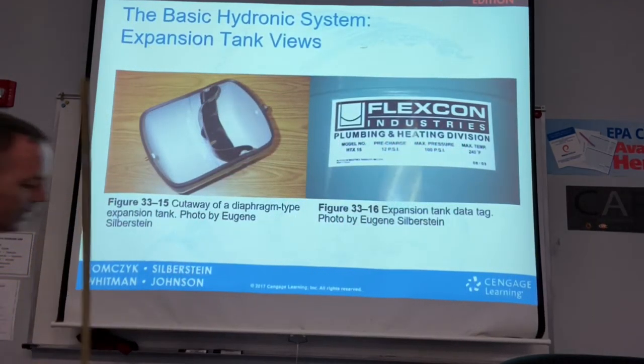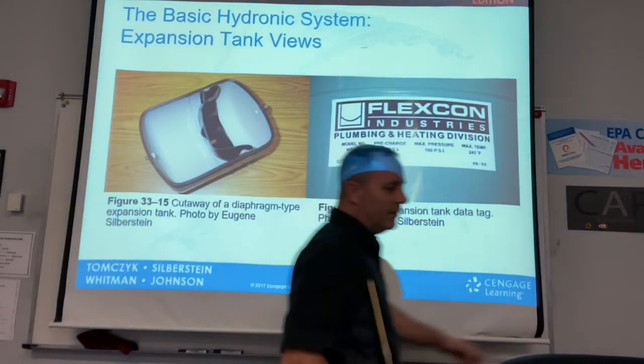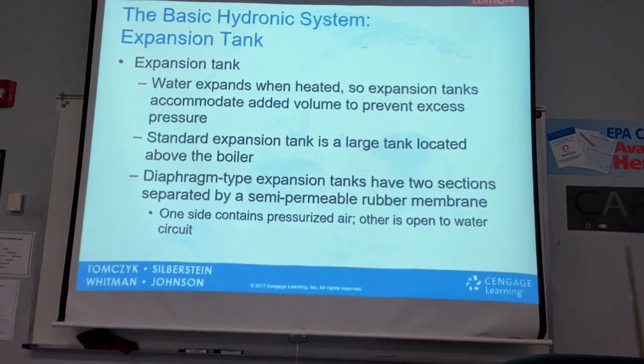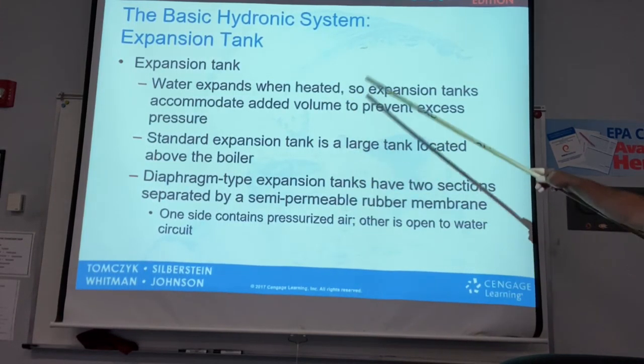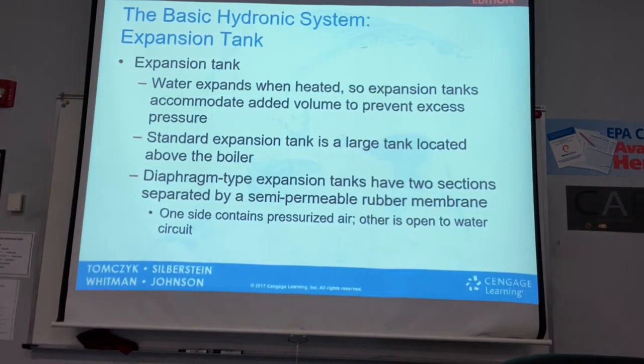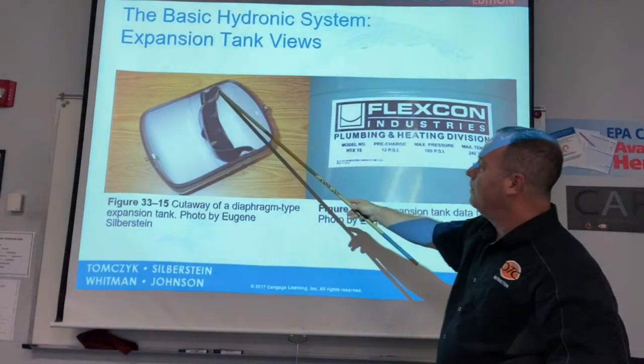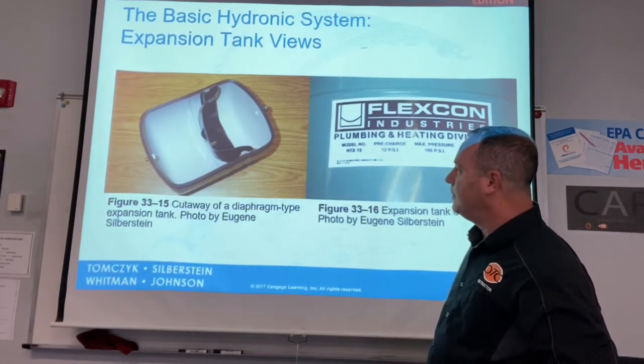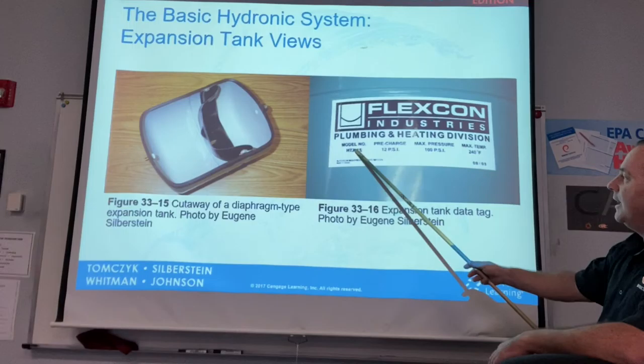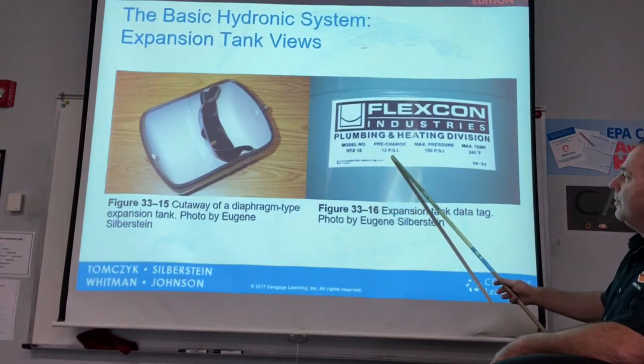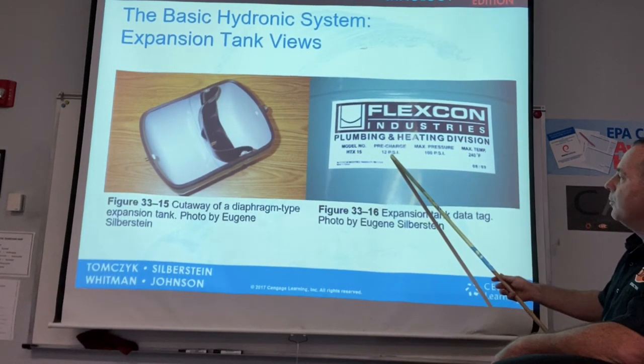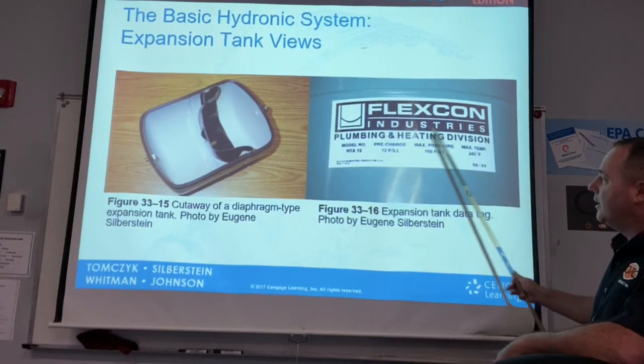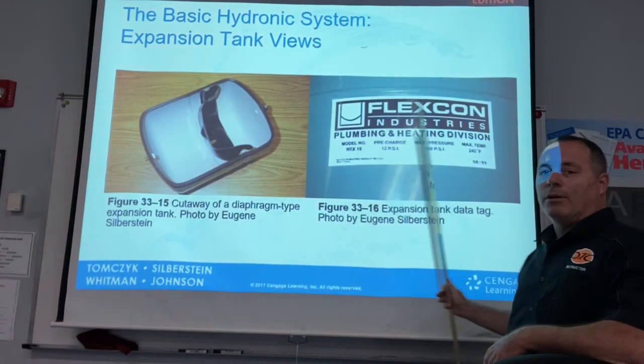In the picture of the expansion tank, you can see the diaphragm inside the tank. Notice it shows the model number and a 12 PSI pre-charge gas pressure written right there on the label.